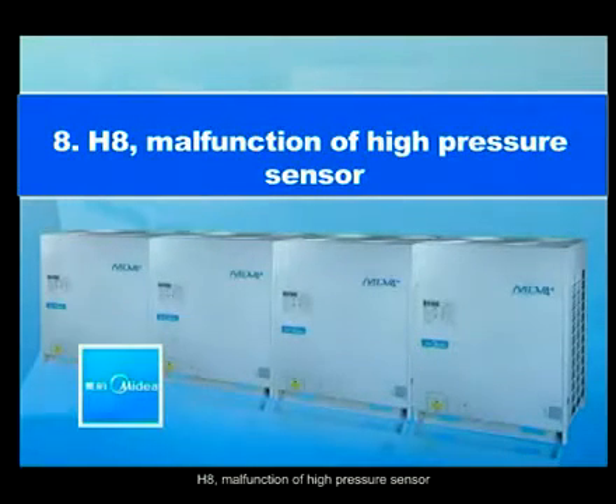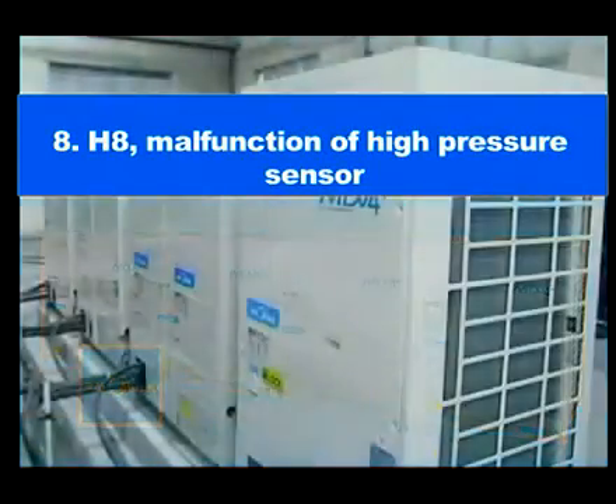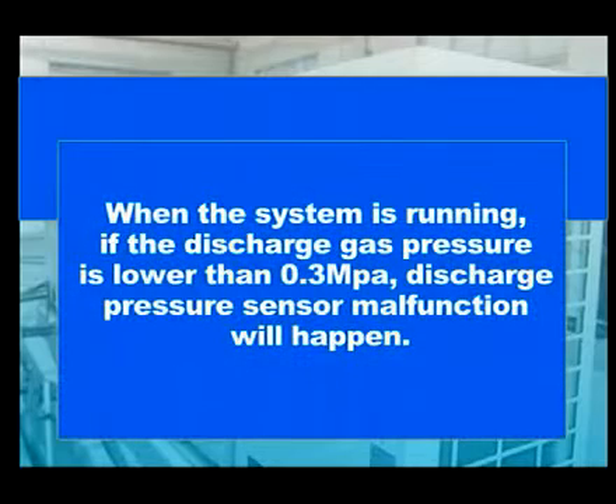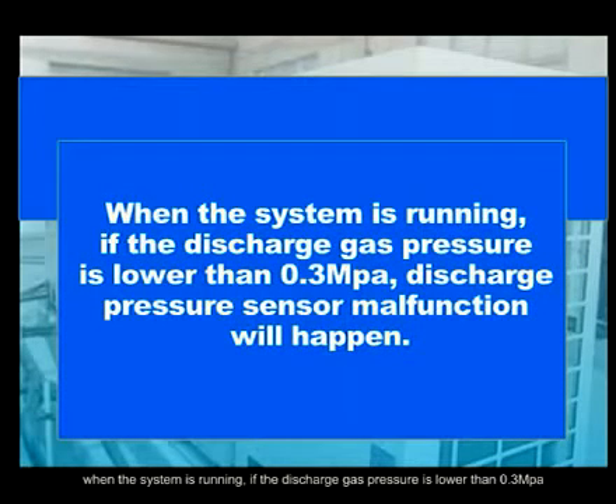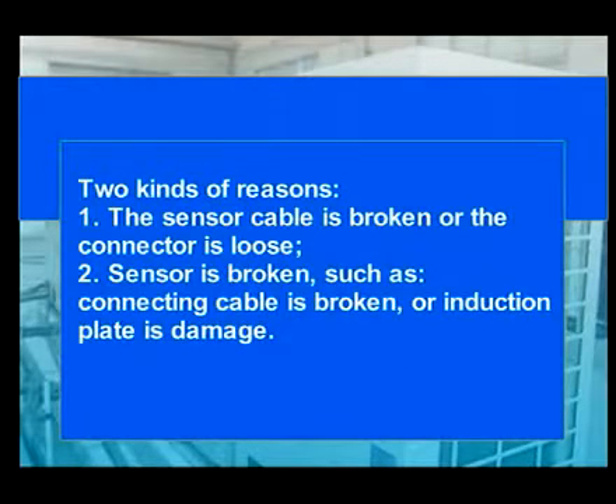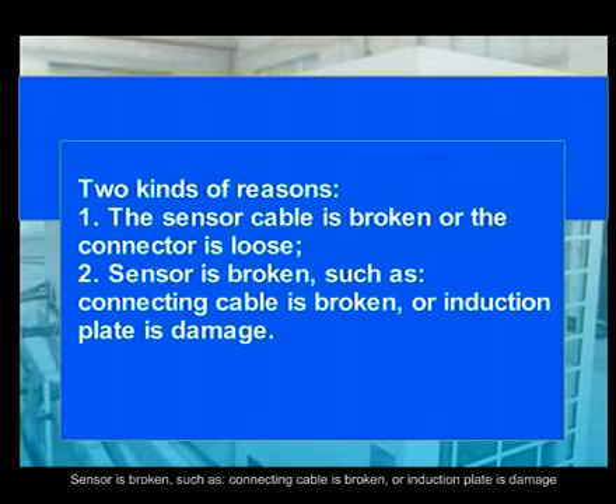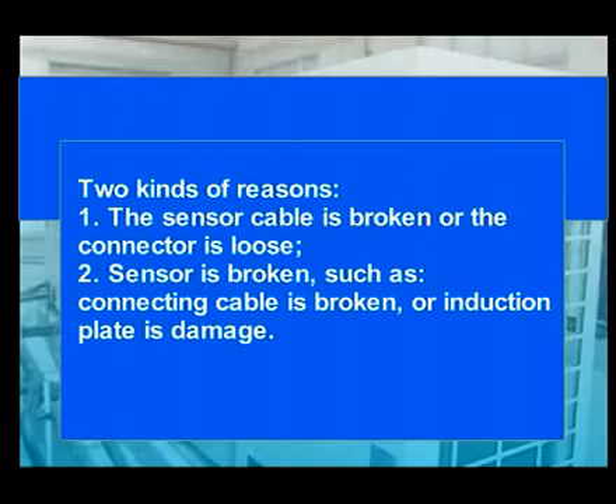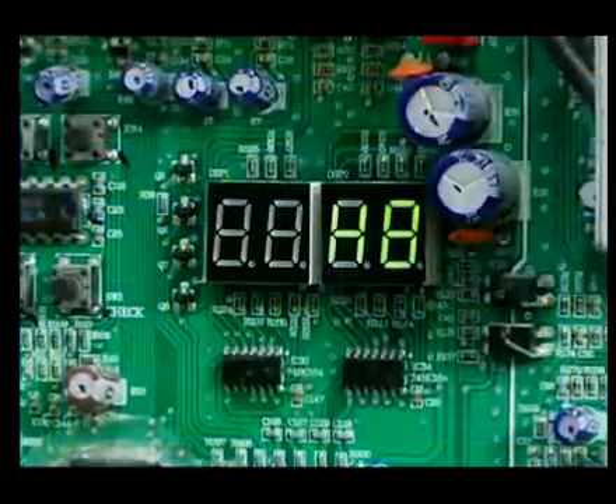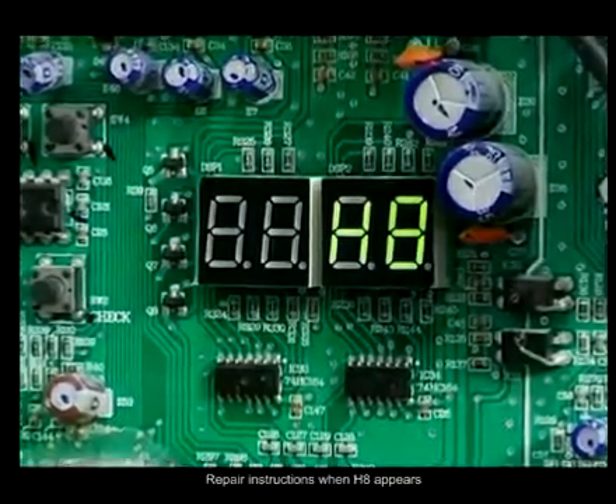H8, malfunction of high pressure sensor. When the system is running, if the discharge gas pressure is lower than 0.3 MPa, discharge pressure sensor malfunction will happen. Two kinds of reasons. 1. The sensor cable is broken or the connection is loosened. 2. Sensor is broken, such as the connecting cable is broken or the induction plate is damaged. Repair instructions when H8 appears.